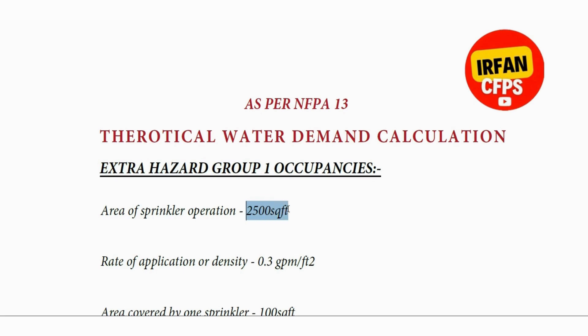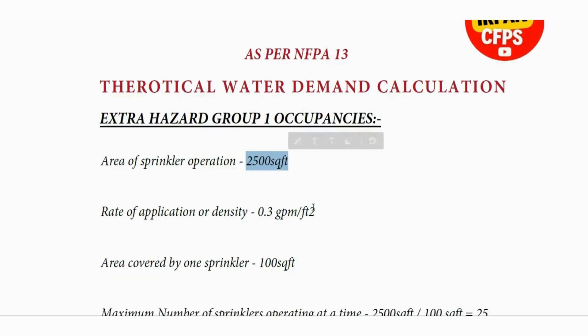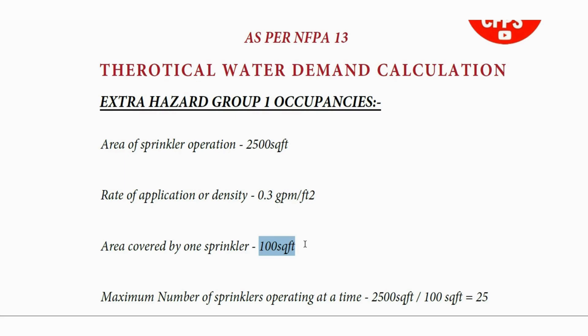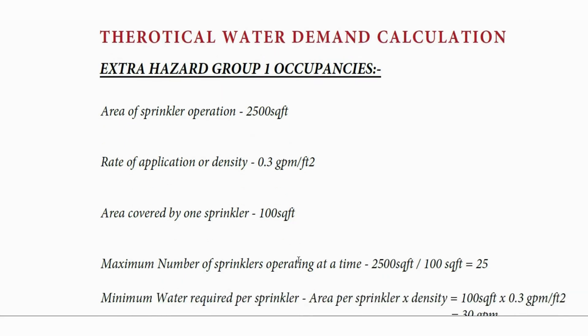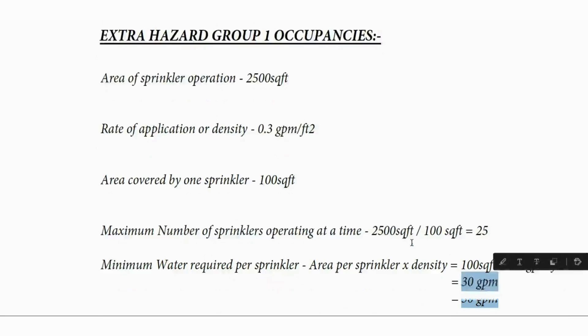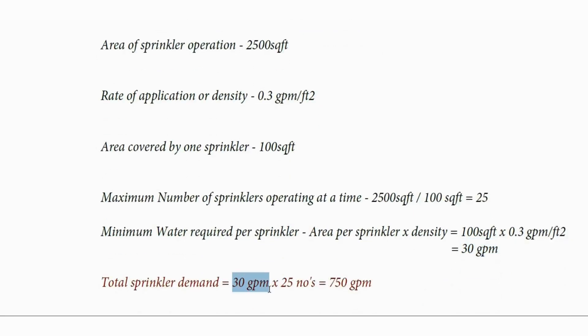For extra hazard group 1 occupancy, the design area will be 2500 square feet and the density will be 0.3 GPM per square foot. The area covered by one sprinkler is 100 square feet — this applies to either extra hazard group 1 or group 2. The maximum number of sprinklers operating at a time will be 25, and the sprinkler flow will be 30 GPM.